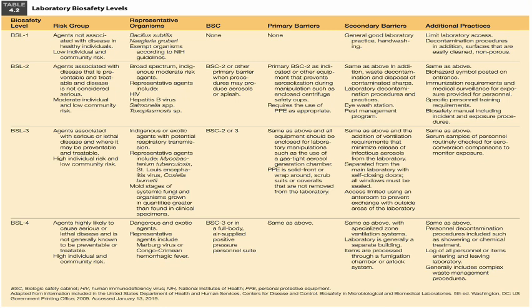Okay? And then for the secondary barrier of BSL4, it needs to have special zone ventilation systems, usually negative pressure, where air is supplied, and then all items are processed through a fumigation chamber or airlock system. And then personal decontamination procedures such as showering or chemical treatment should be done before you go out of the BSL 4 facility. And the in and out of the personnel or items entering and leaving the laboratory should be consistently logged. Okay? And BSL 4 generally includes complex waste management procedures.